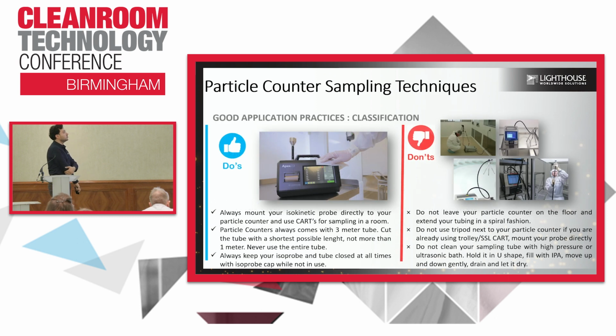There are a couple of do's and don'ts for the classification. Always mount your isokinetic probe directly to your particle counter, as we already mentioned. And each particle counter comes with 3 meters of tubing. This is an industry standard for the manufacturers because we are sending it out to different industries. But keep in mind, you have to cut it based on your requirement for the classification. Never use the entire tube alone.